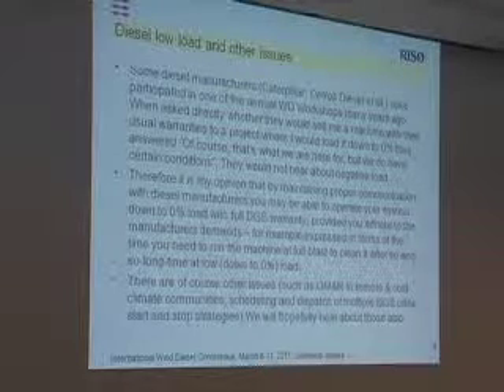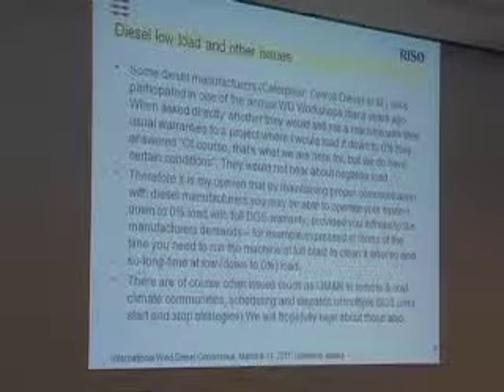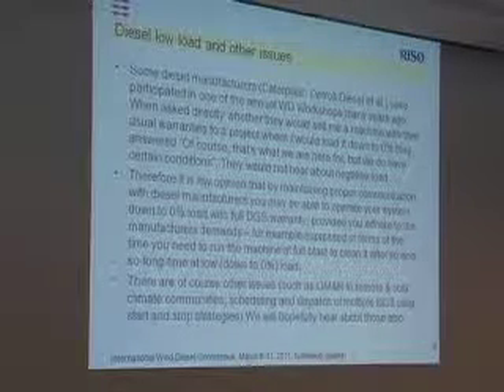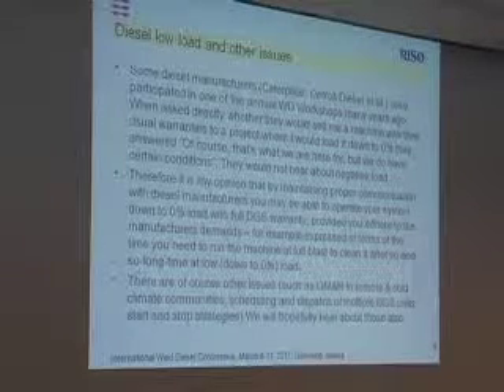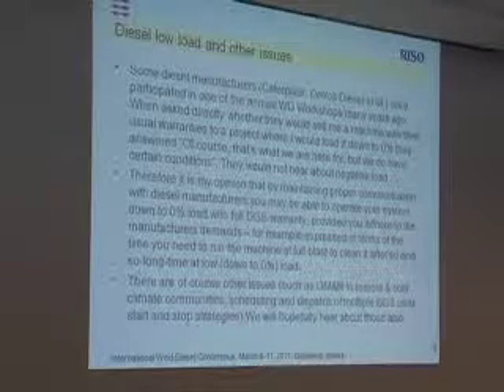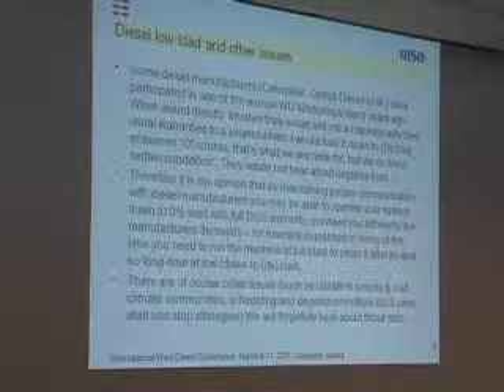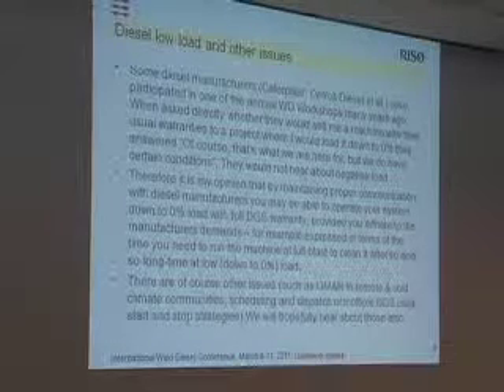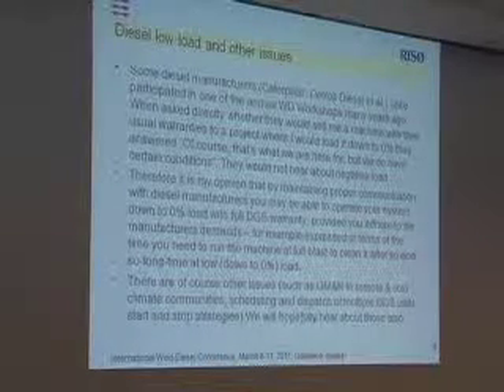One thing I know all diesel manufacturers have in their drawer, without showing the customers, is a curve saying that if you have the diesel working too long at too low load, you need afterwards to blast it through for a certain time to clean it out. That's one thing. I also have a method that includes mineral water, but there are many ways to deal with that.